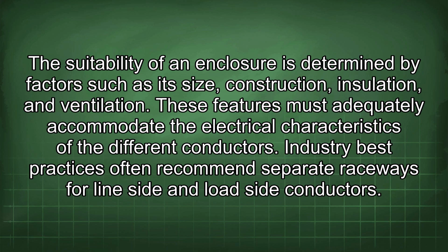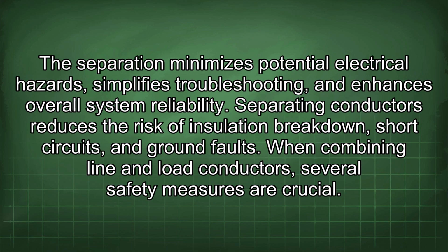Industry best practices often recommend separate raceways for line side and load side conductors. The separation minimizes potential electrical hazards, simplifies troubleshooting, and enhances overall system reliability. Separating conductors reduces the risk of insulation breakdown, short circuits, and ground faults.